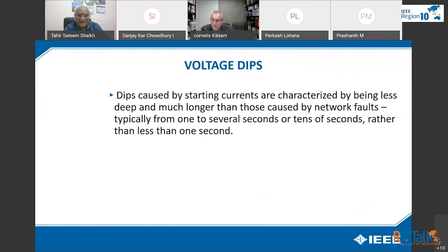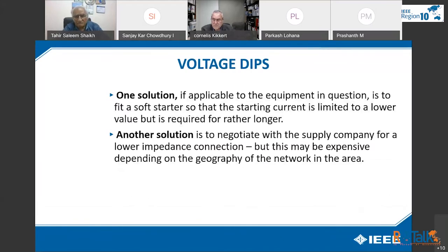Dips caused by starting currents are characterized by being less deep and much longer than those caused by network faults, typically from 1 to several seconds, or tens of seconds, rather than less than 1 second. One solution for this voltage dip is to have a soft starter in the circuit. Your drive will run on a ramp, and there will not be much voltage dip on the system. Another solution is to negotiate with the supply company for a lower impedance connection. In our country, we don't have this concept, and no utility can give you a low impedance connection.